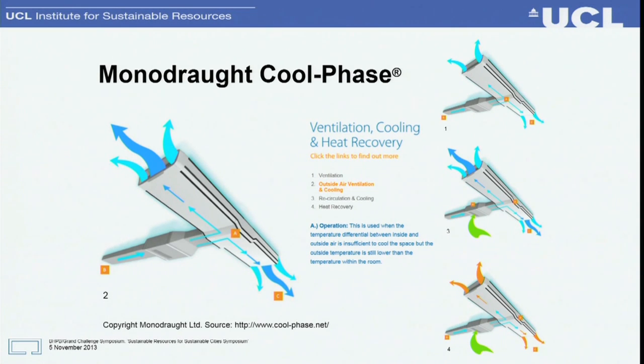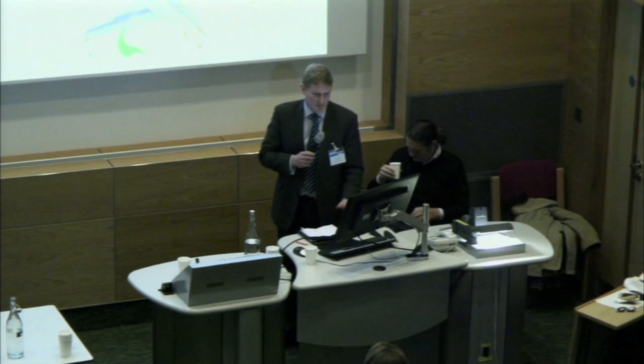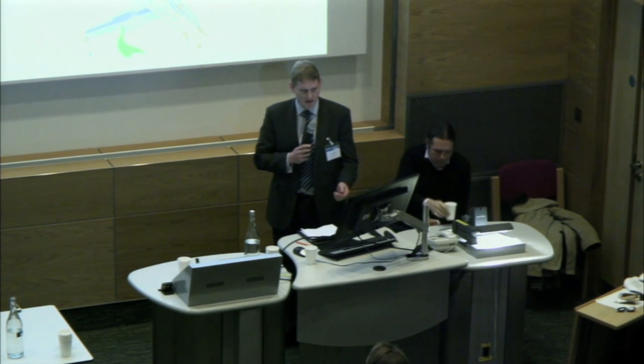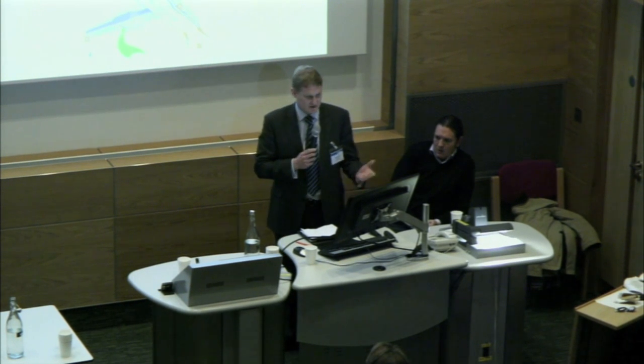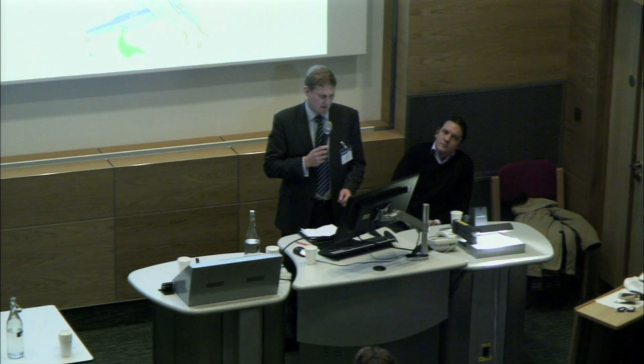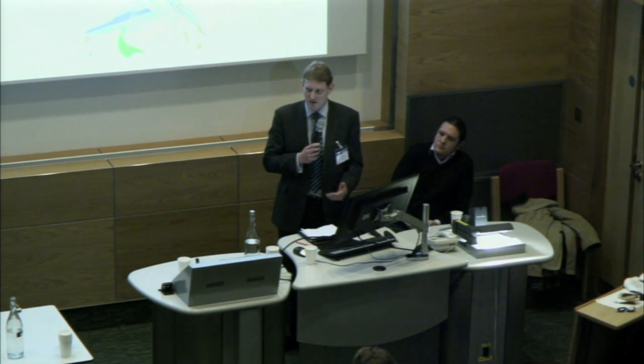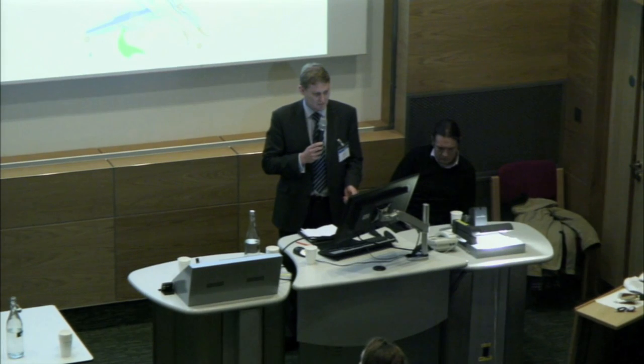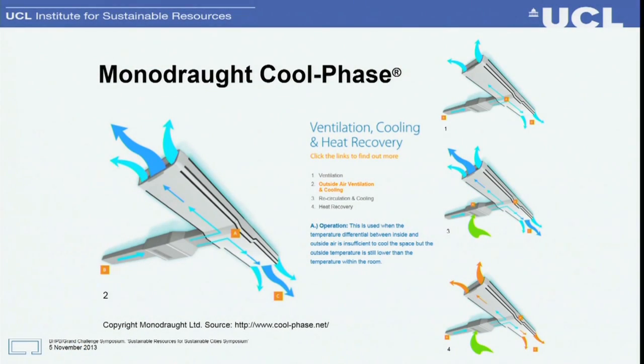My name's Nick Hopper. I'm the technical director for Monodraught, and I've been asked to give you a talk about a commercial product that we launched in 2011. It's a ceiling-mounted phase change store — unlike the research project, which is passive-based, this is an active type system. It has an air handling unit mounted in the centre, and the phase change material is mounted either side of it, configured like a heat exchanger. This makes it highly effective at charging and discharging the energy store from nighttime through to daytime. The unit is modular and ceiling-mounted, so it can fit in most applications. A duct connects it to the outside; during the night we bring in cool nighttime air and charge the phase change material, which is then discharged during the day, providing a cooling effect.